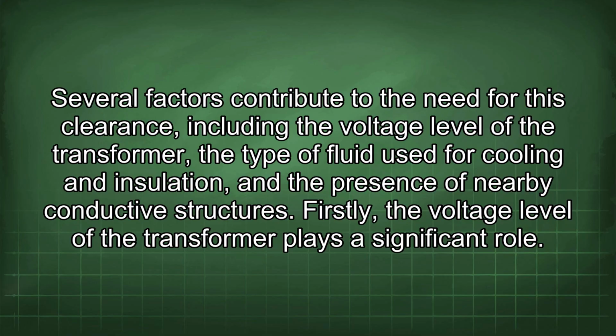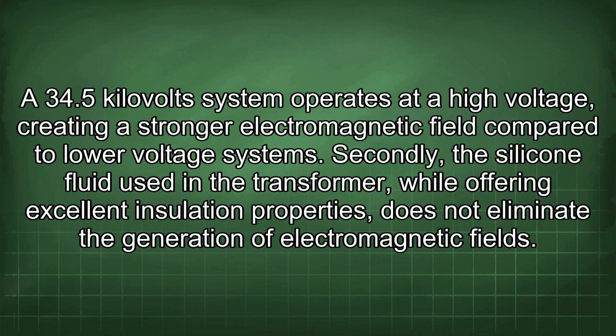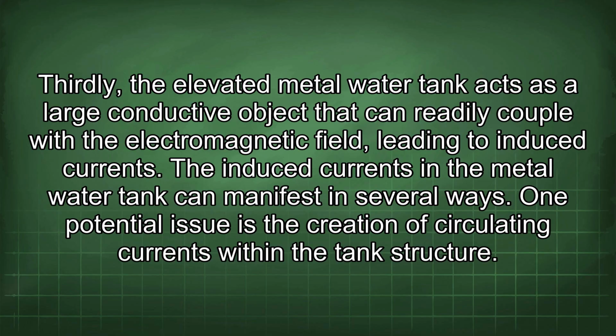Firstly, the voltage level of the transformer plays a significant role. A 34.5 kV system operates at a high voltage, creating a stronger electromagnetic field compared to lower voltage systems. Secondly, the silicone fluid used in the transformer, while offering excellent insulation properties, does not eliminate the generation of electromagnetic fields. Thirdly, the elevated metal water tank acts as a large conductive object that can readily couple with the electromagnetic field, leading to induced currents.